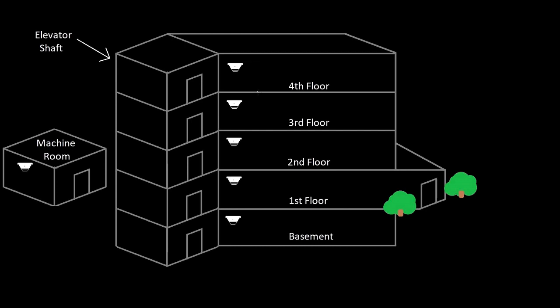They will call that primary because it's a smoke detector for the primary floor. When we get into the relays I'm going to explain how I kind of mitigate that. We're going to group every detector that's going to send the car to the primary floor, which based on these lovely bushes we can tell that that's the main floor where the exit of the building is. So floors four, three, two, and basement are all going to be in the same group that sends the car to the first floor.